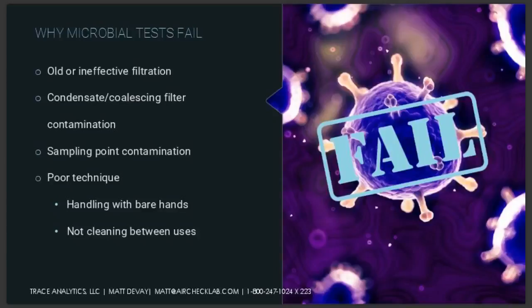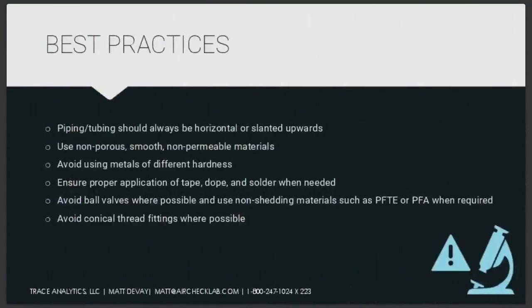All right, so we're about wrapping up here. We're just going to go through some best practices. Your piping and tubing, particularly at point of use or sampling points, should always try to be horizontal or slanted upwards so that you don't have liquid condensates dripping down. Use non-porous, smooth, non-permeable materials where you can. Definitely avoid connections using metals of different hardness. If you do, try to go for face seal or solder joints instead of conical threads. Always ensure the proper application of your tape, dope, and solder.